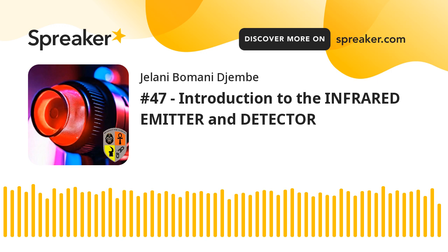Photodiodes, on the other hand, are semiconductor devices that produce a current when exposed to infrared radiation, while pyroelectric detectors generate a voltage in response to changes in temperature caused by infrared radiation. In addition, technicians should be aware of the factors that can affect the performance of infrared emitters and detectors, such as temperature, ambient light, and interference from other sources of infrared radiation.